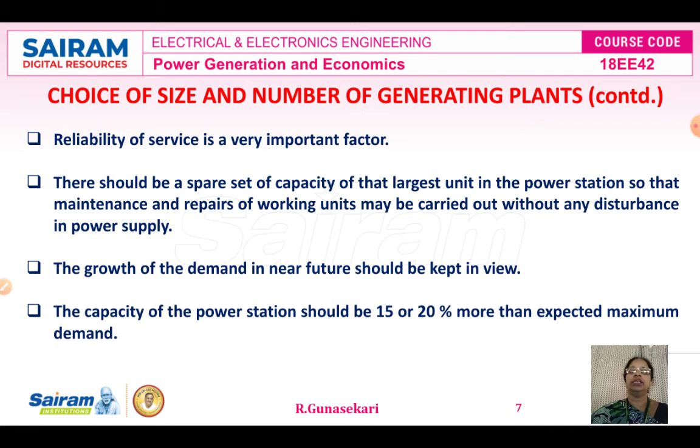The next factor, reliability of service, is very important. As I have told, reliability means maintaining voltage, maintaining frequency, and maintaining uninterrupted power supply. There should be a spare capacity equal to the largest unit in the power system, so that maintenance and repair of the working units may be carried out without any disturbance in the power supply. The growth of demand in the near future should be kept in view.